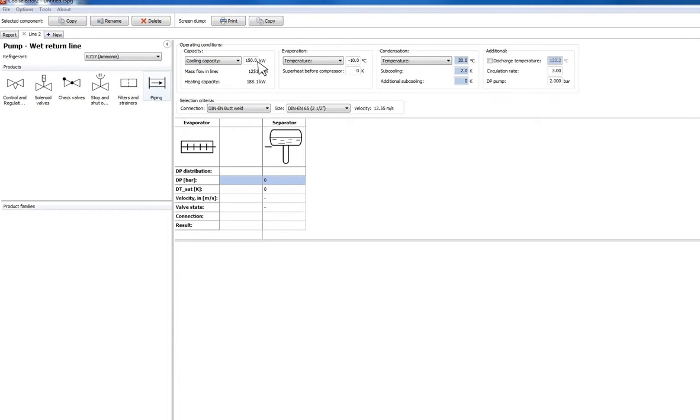Let's look at 150 kilowatts, then minus 10, temperature 30 degrees Celsius, and a circulating rate of 3, and we have connection DIN-EN butt weld.